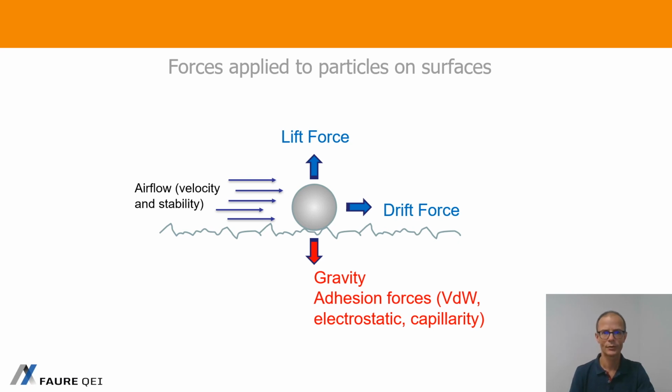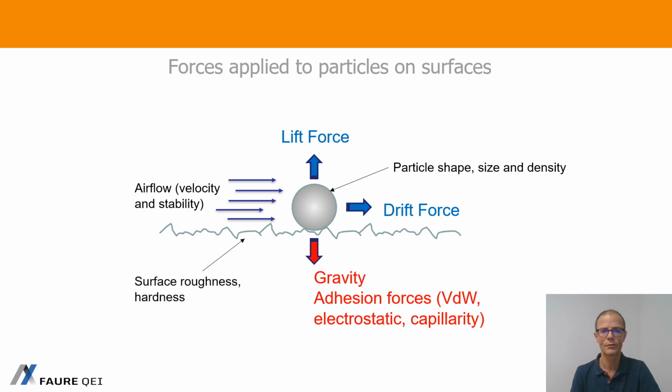Resuspension of particles is an important topic for us as it can change the concentration of particles transferred inside a clean environment like a clean room. Lift and drag forces, what we call aerodynamic forces, may overtake the adhesion forces and gravity that maintain particles on surfaces. So surface quality and particle characteristics both have an influence on results. Particle shape, size, and density can change the way particles adhere to surfaces, and the surface roughness or hardness is an important parameter too.